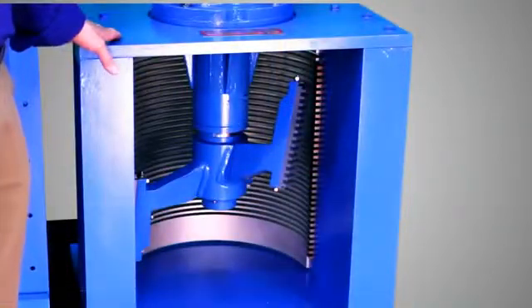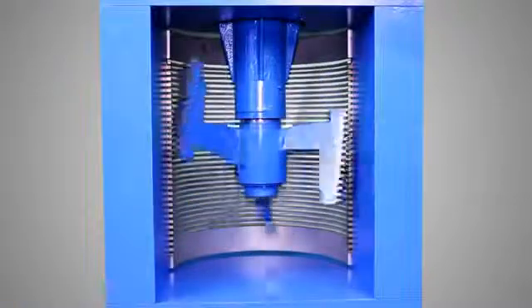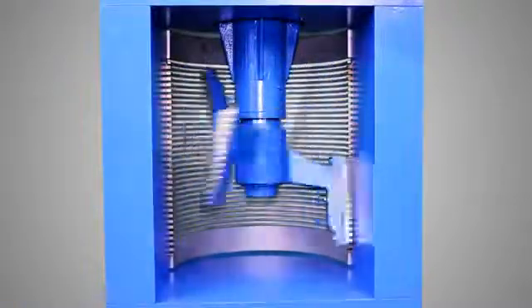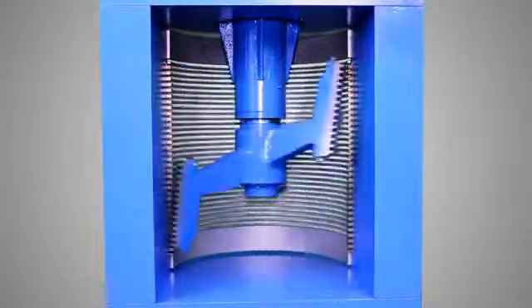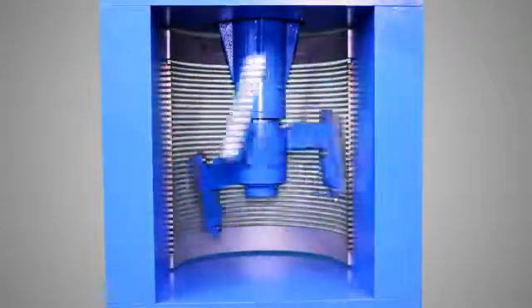Here's our Diminutor. This open channel comminuter features the easiest maintenance and is the proven favorite of users worldwide because it's so dependable. In the Diminutor, rotary cutters sweep the solids into adjacent stationary cutters, shearing and tearing them to a size small enough to pass through the unit's screen. The Diminutor's cutters are individually replaceable and swappable, and another great feature is that it has no seals or bearings located in the channel bottom.